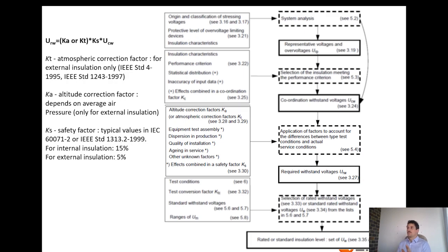All right, so we went through the study analysis. Then we had a coefficient which takes into consideration the representative overvoltage method we selected. Now you have to add coefficients which are based on the environment where your network is. When you do the simulation in the EMTP, if your circuit is in a polluted place or in a place which is cleaner, it will not change so much. Same thing if it's at high altitude or not, it will not change so much. It will change the line modeling a little bit, but that's it. And so the result you get, you have to use coefficients to adapt and take into consideration, for example, the atmospheric correction factor, the altitude correction factor, and of course, like for all engineering studies, a safety coefficient, because of all the errors that could be made in parameter identification and so on. Here you have some typical values, but I invite you to take a look at the standards to get more precise values.